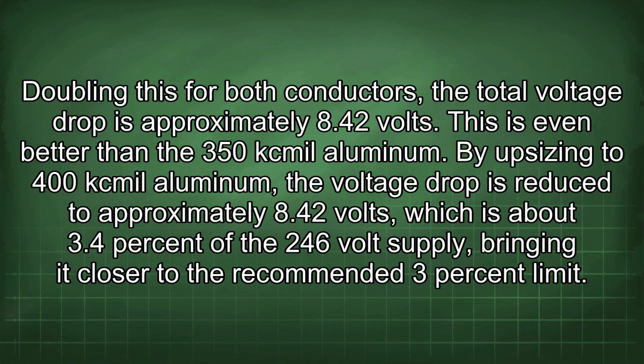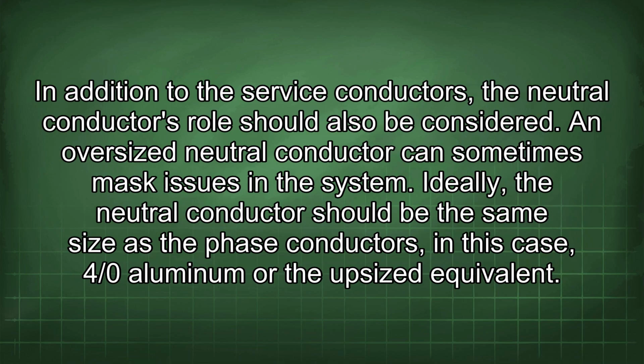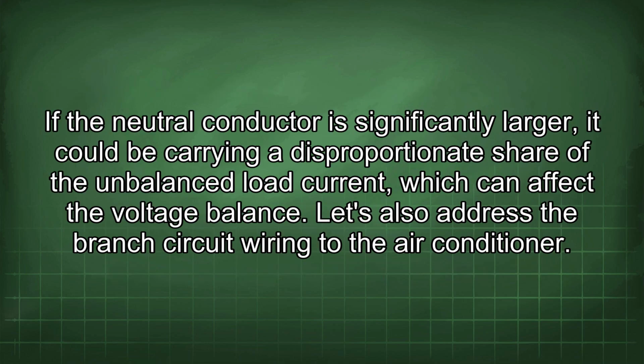By upsizing to 400 kcmil aluminum, the voltage drop is reduced to approximately 8.42 volts, which is about 3.4% of the 246-volt supply, bringing it closer to the recommended 3% limit. In addition to the service conductors, the neutral conductor's role should also be considered. An oversized neutral conductor can sometimes mask issues in the system. Ideally, the neutral conductor should be the same size as the phase conductors, in this case, 4/0 aluminum or the upsized equivalent. If the neutral conductor is significantly larger, it could be carrying a disproportionate share of the unbalanced load current, which can affect the voltage balance.